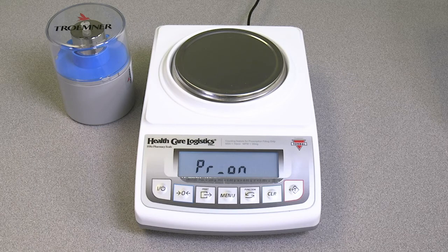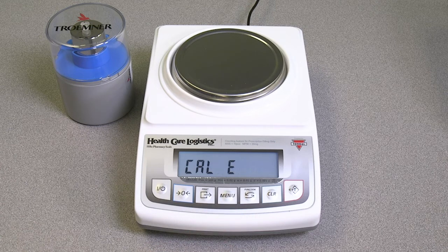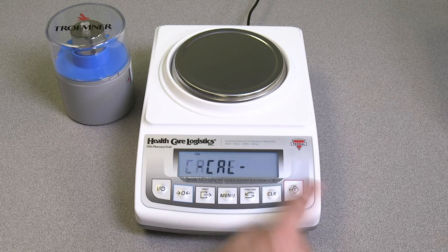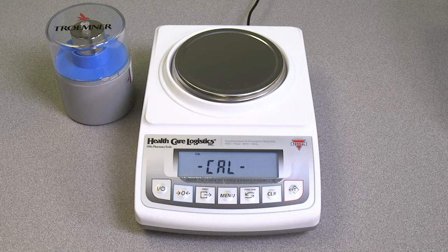This will put the scale into calibration mode, which you will know because of the loud tone from the scale. You will also see PR displayed on the screen. Enter the weighing mode by pressing Menu. The tone will then stop. When the Calibration option appears on the screen, press the T key. The scale will then begin to tare. Calibration will appear on the screen for a few moments, then a series of dashes.